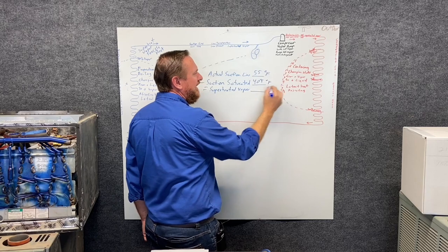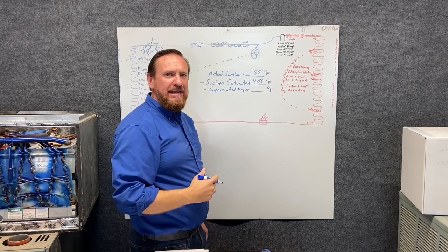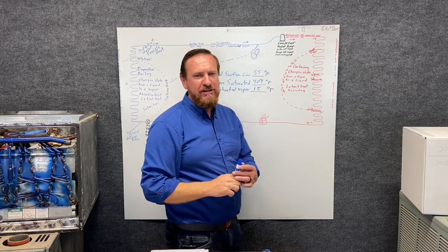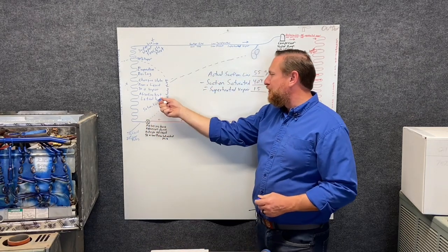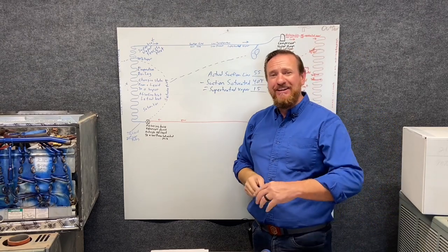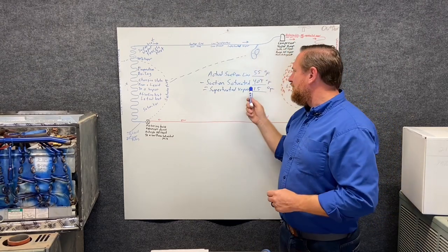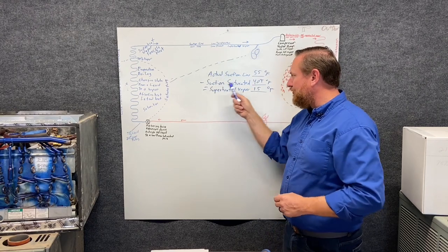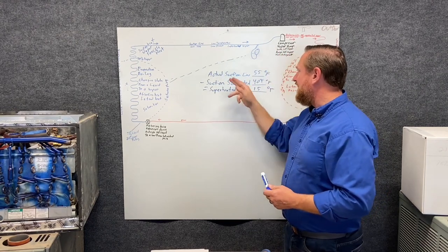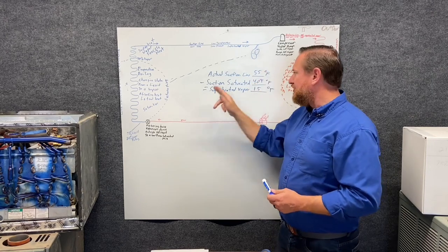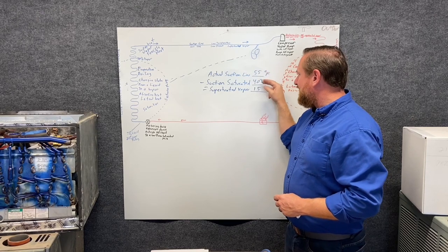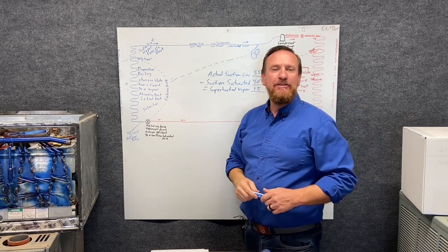Blank degrees Fahrenheit, and in this case, I have superheated my refrigerant 15 degrees above its saturation temperature. Saturation was 40 degrees. I've added an additional 15 degrees of measurable, sensible heat to the refrigerant. So this is our formula. If you write this down word for word, anytime you're doing superheat, you just simply plug the numbers in. Hey, what's the actual suction line? Put the number in. Suction saturated, PSIG converted temperature. You write that number in. This number minus that number is how much superheated vapor that you have.